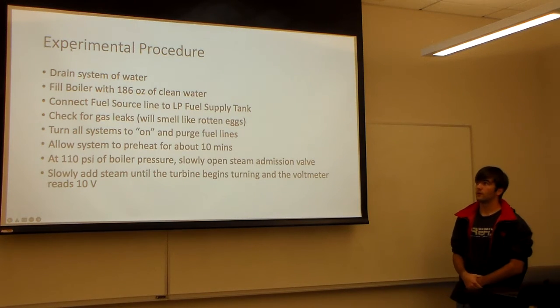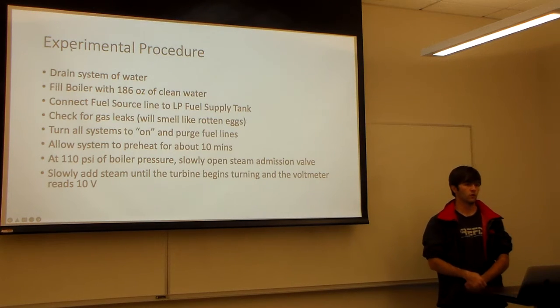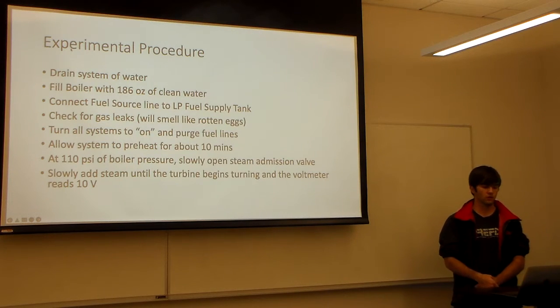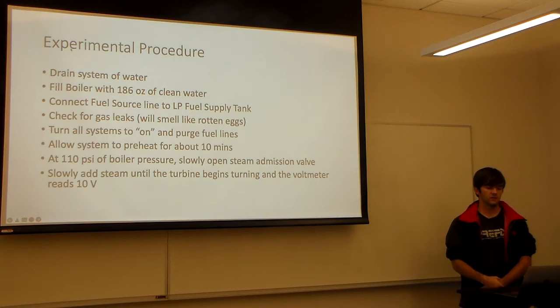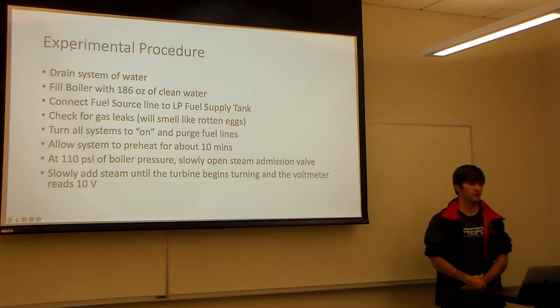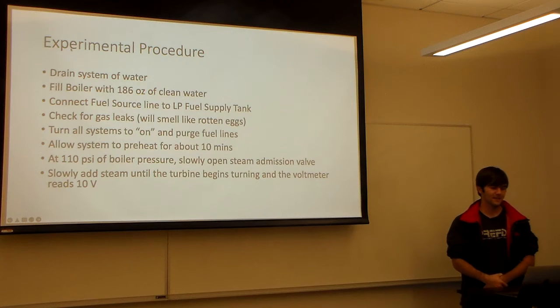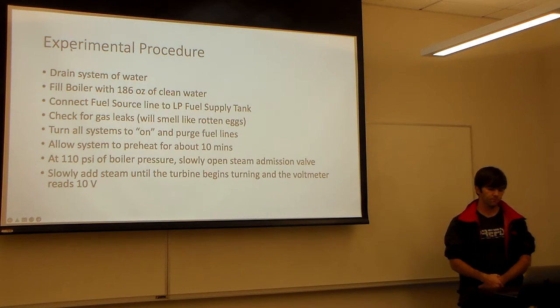Just a generalized experimental procedure. We have to drain the system of water before we start so we know how much water is in it. We fill the boiler with 186 ounces of clean water. We connect the fuel source line to the fuel supply tank. We check for gas leaks to make sure we're not about to blow up everybody. And then we turn all systems to on and purge the fuel lines and allow the system to preheat for about 10 minutes to make good quality steam.